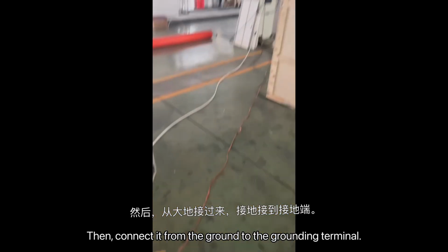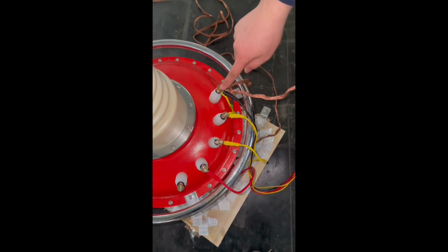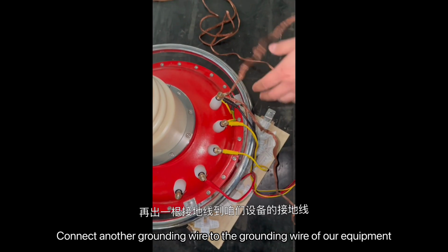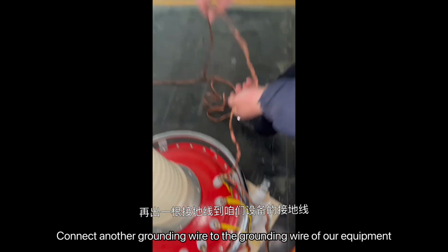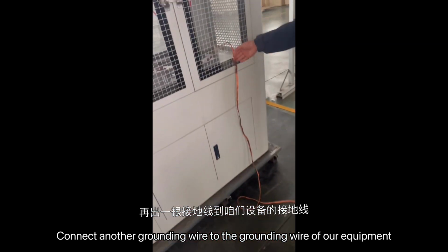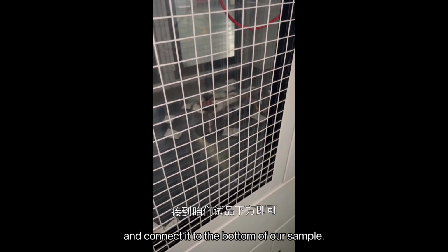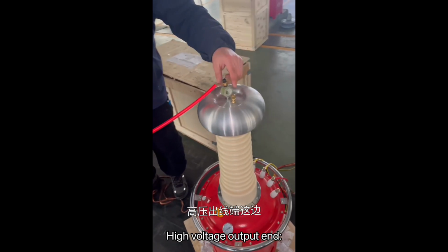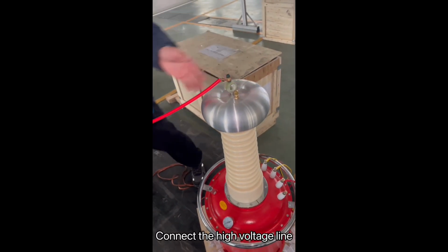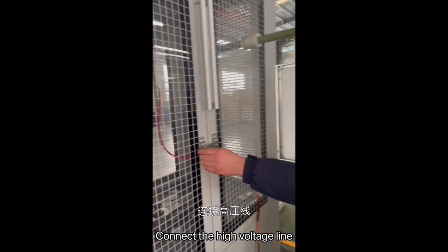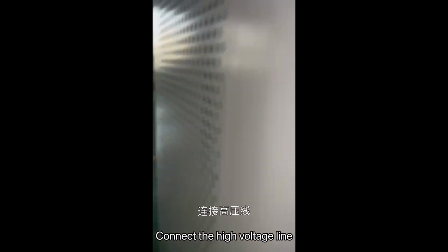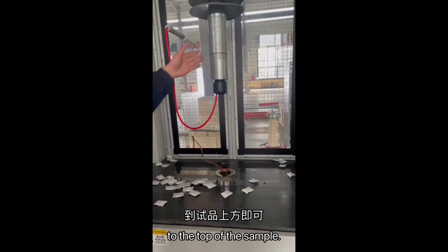Then, connect it from the ground to the grounding terminal. Connect another grounding wire to the grounding wire of our equipment, and connect it to the bottom of our sample. High voltage output end. Connect the high voltage line to the top of the sample.